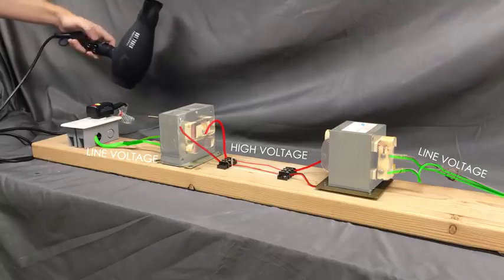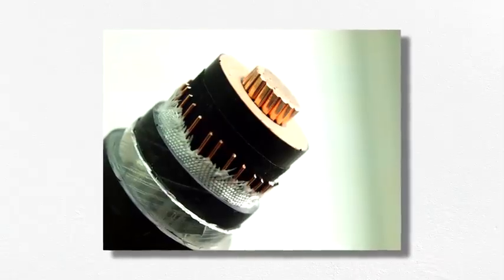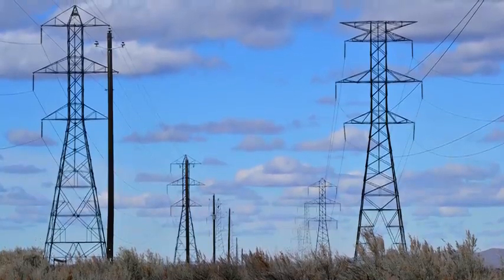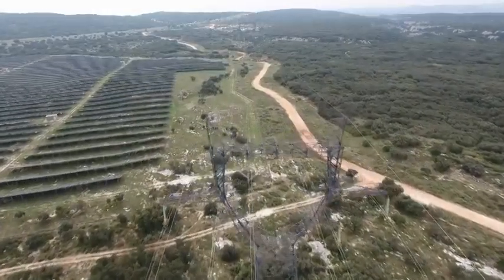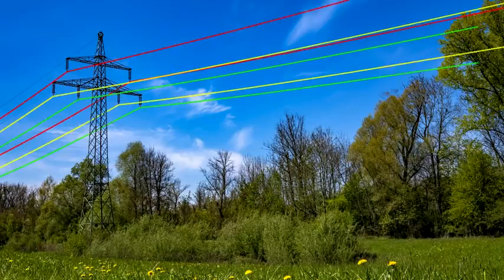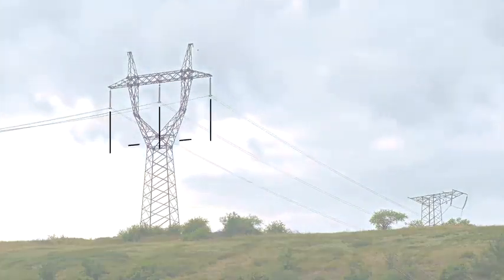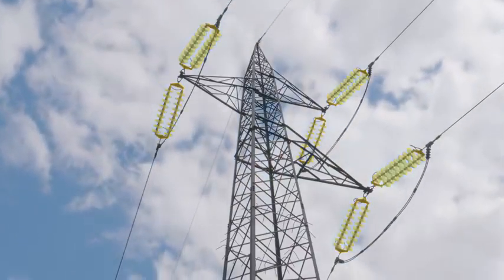What we've also done is make things much more dangerous. You can think of voltage as electricity's desire to flow — high voltage means that the power really wants to move and will even flow through materials we normally consider non-conductive, like the air. The engineers designing high voltage transmission lines have to make sure the lines are safe from arcing and other dangers. Most long distance power lines don't use insulation around the conductors themselves, as insulating this way would have to be so thick it wouldn't be cost effective. Instead, most of the insulation comes from air gaps — simply spacing everything far enough apart. Transmission towers and pylons are really tall to prevent anyone or any vehicle from inadvertently getting close enough to the conductors to create an arc. Bulk electricity is transmitted in three phases, which is why you'll see most transmission conductors in groups of three, each phase spaced far enough apart from the others to avoid arcing between the phases.